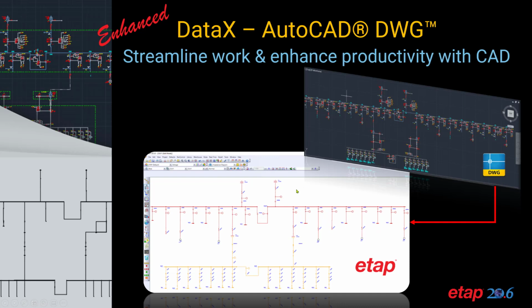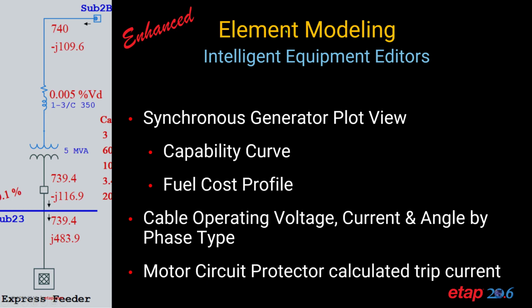You can simply import the diagram into ETAP, but in ETAP 20.6 you now also have the ability to go the other way, from ETAP directly into AutoCAD, and produce deliverables in a native DWG format. The element modeling has also been enhanced in ETAP with, of course, the generator plot views for capability curve and fuel cost profiles, but we have also added the ability for cable operating voltage, current, and angle to be displayed directly inside the cable editor. The motor circuit protector calculated trip currents are also visualized directly inside the element editors.